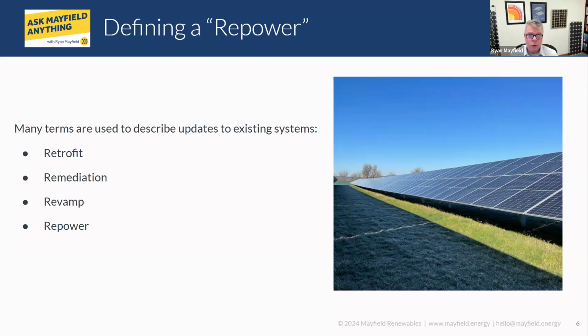around utilities, and whether you need to restructure any agreements or net metering agreements. When working with our clients and contractors, one of the big things is as long as you're not increasing that AC capacity, that's been the line in the sand for us. So if you have a 500 kilowatt AC output inverter and you're replacing it with 500 kilowatt inverters, or an aggregated capacity of 500 kilowatts, you're not changing your net metering agreement.